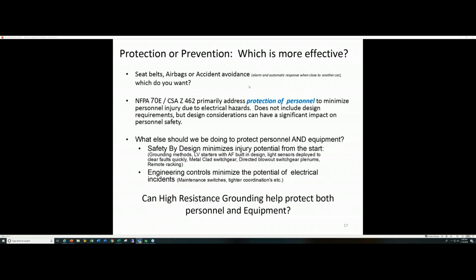Well, you've got to do safety by design. Many of you have heard that before. Of course, you design the safety in as we're building stuff and designing stuff and engineering stuff, so we eliminate the injury potential from the start. That would include maybe some arc flash rated starters, I-Gard starters, metal clad switchgear, grounding methods, direct blowout switchgear plenums, things like that, remote racking so the employee doesn't physically have to be in the boundaries of the arc flash and the incident energy that may happen.